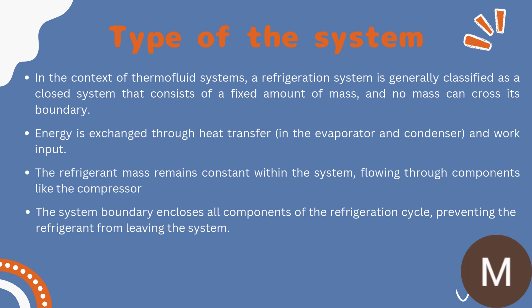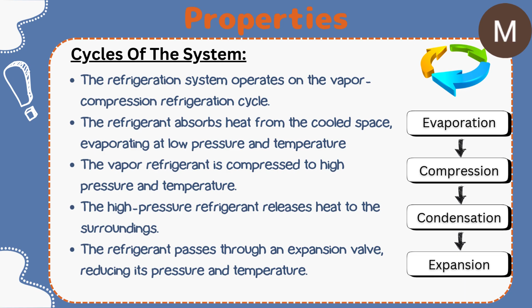This is the cycles of the system. The refrigeration system operates on the vapor compression refrigeration cycle. The refrigerant absorbs heat from the cool space, evaporating at low pressure and temperature. The vapor refrigerant is compressed to high pressure and temperature. After that, the high pressure refrigerant releases the heat to the surroundings. And the last one, the refrigerant passes through an expansion valve, reducing its pressure and temperature.